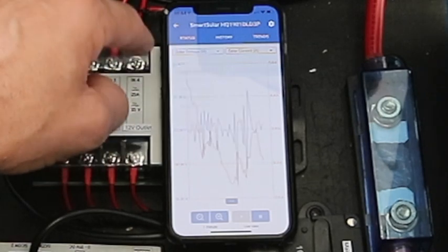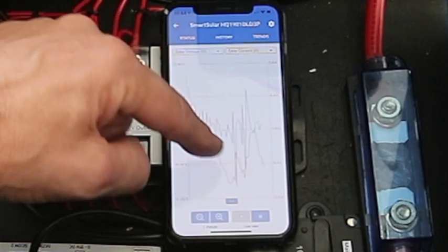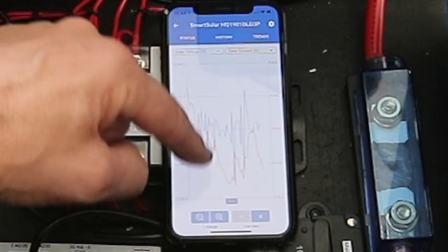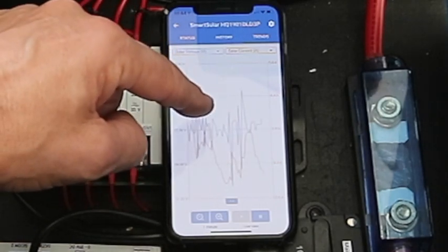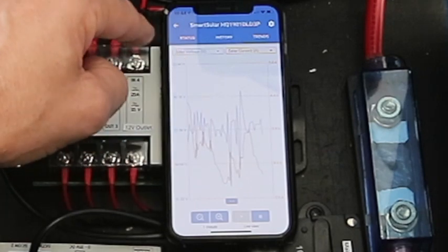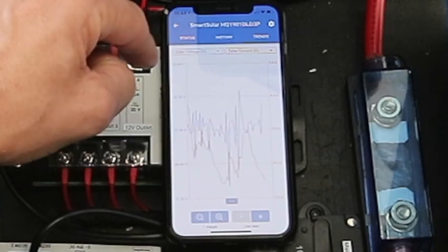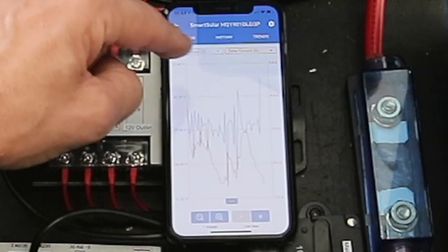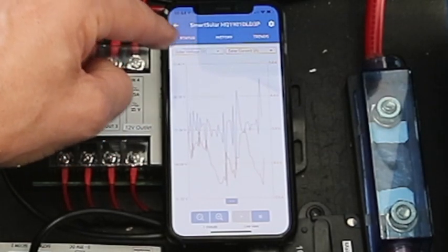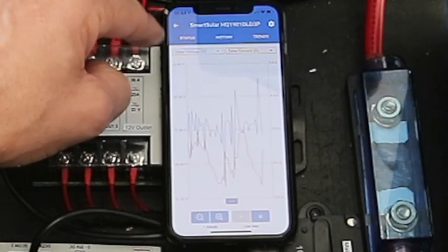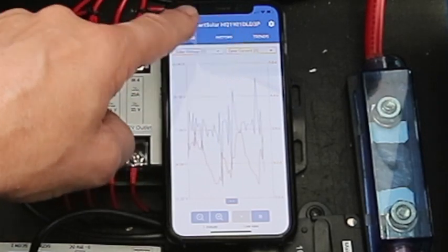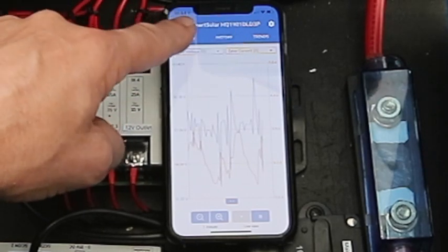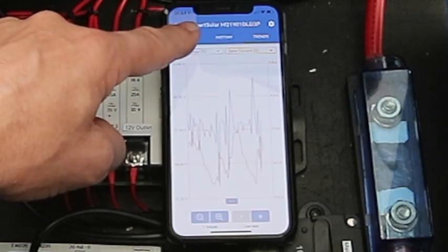After we cover up a panel at a time, if I come up here, I want to see what the solar voltage is off the panels that aren't covered up so that we can see that all the panels are performing in a consistent way to spec. So the trend is just fantastic for commissioning.